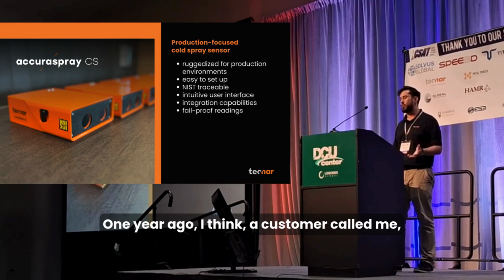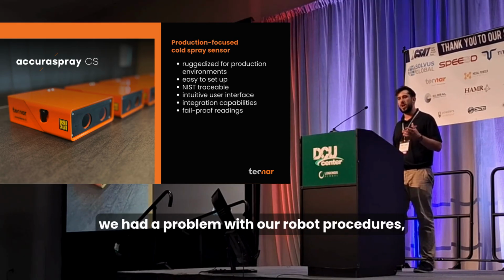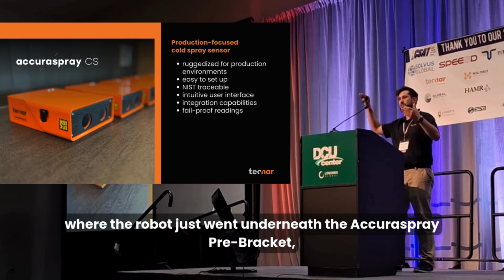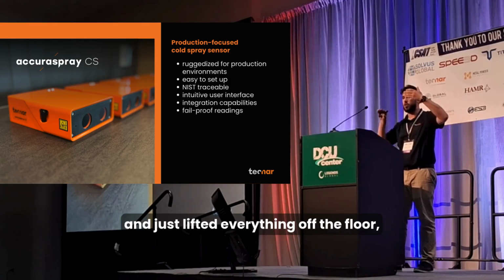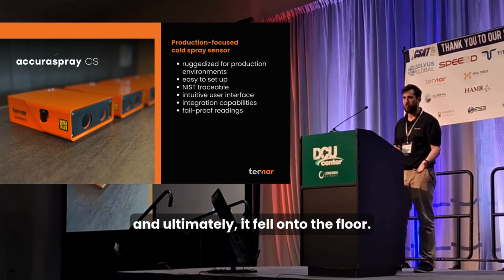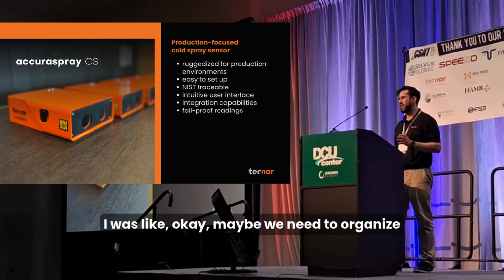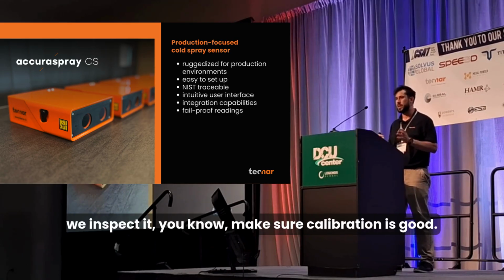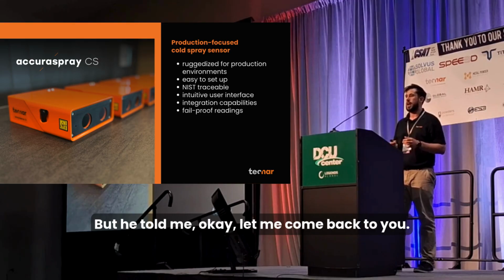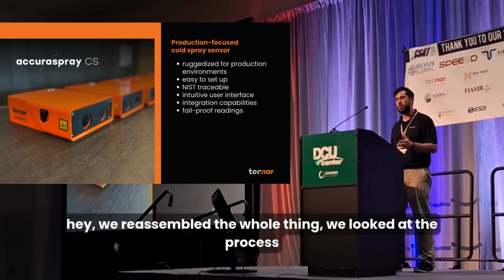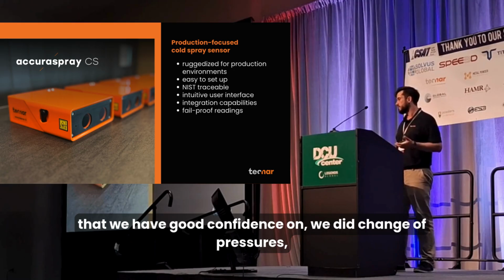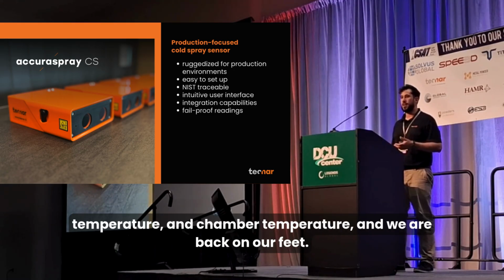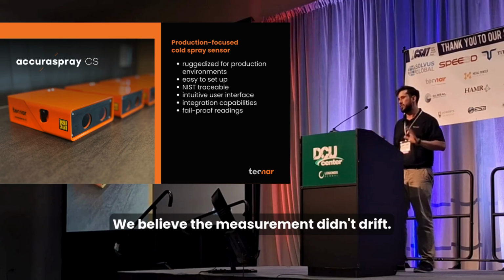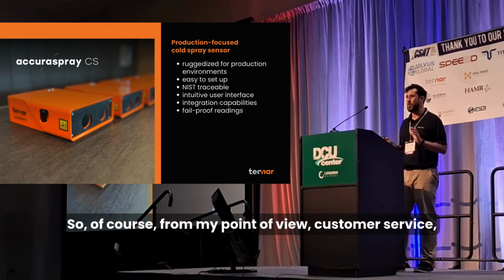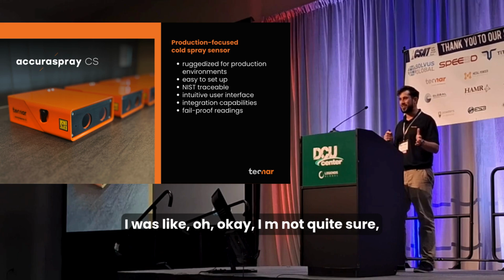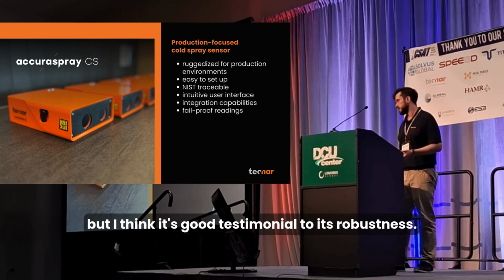I have kind of a funny story. About a year ago, a customer called and said, 'Hey, we had a problem with our robot procedures where the robot went underneath the Accuraspray bracket, lifted everything off the floor, took the bracket out with the sensors, and it fell onto the floor.' I said, okay, maybe we need to organize an RMA so it comes back, we inspect it, make sure calibration is good. But they said, let me come back to you. The day after, they called and said, 'We reassembled the whole thing, looked at the process we have good confidence on, did a change of pressures, temperature and chamber temperature, and we're back on our feet. We believe the measurement didn't drift.' From my point of view as customer service, I wasn't quite sure, but I think it's a good testimonial to its robustness.